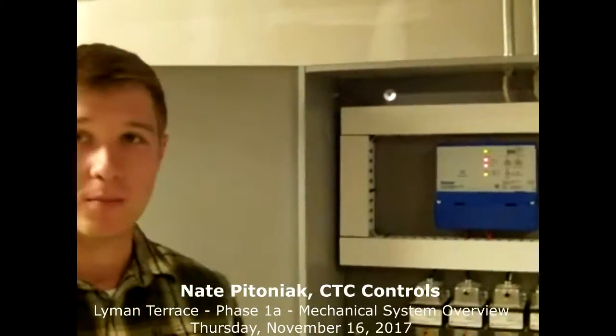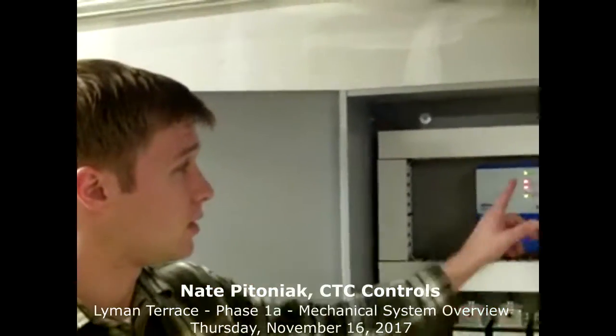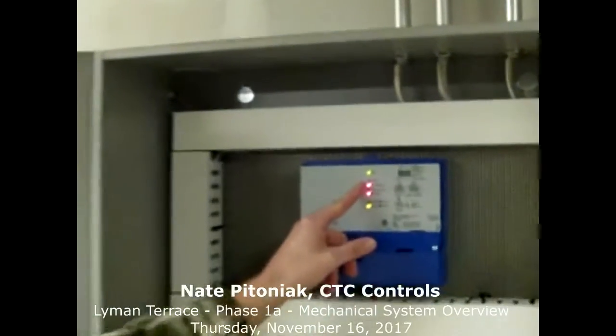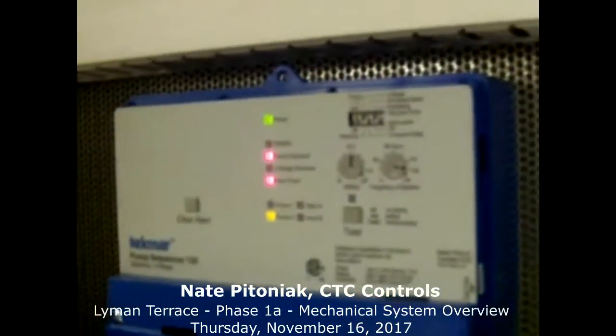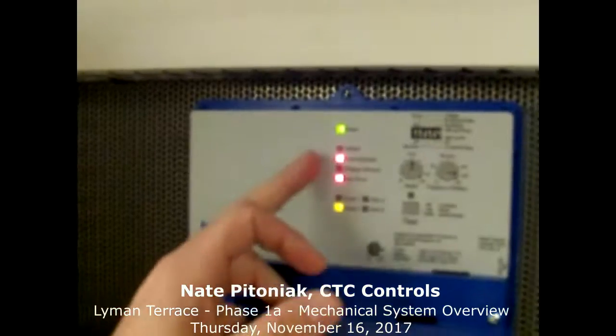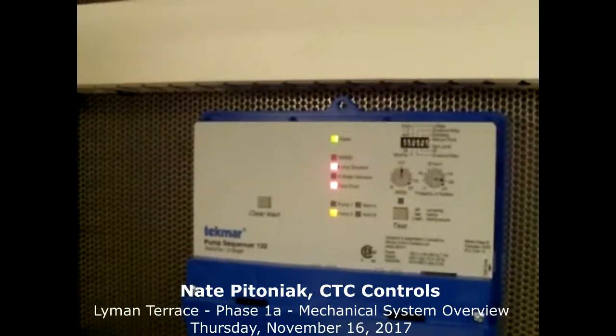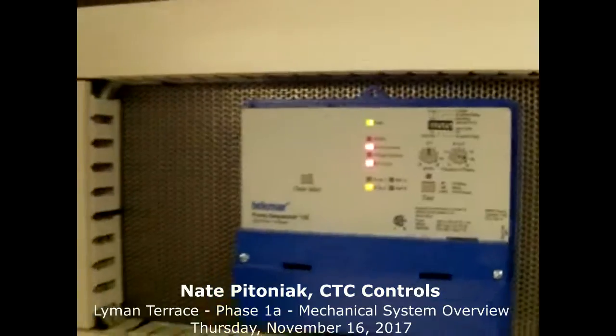So going off what Joe and John mentioned, this tekmar system is in place to control the system pumps. We did our lead lag, right now it's set for 168 hours. The only thing I think we didn't touch on so far was the warm weather shutdown. Right now it's set for 70. Every time it's 71 or above outside, both pumps are down. When that does happen, you'll see your warm weather shutdown illuminated. And then on the other side, say it's chilly outside, you'll see your pump demand illuminated. And that's just a quick reference to say, building wants heat.